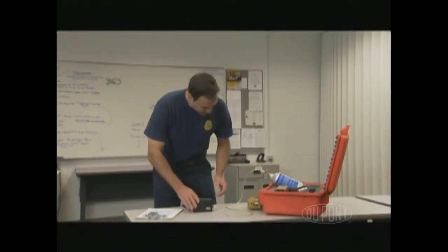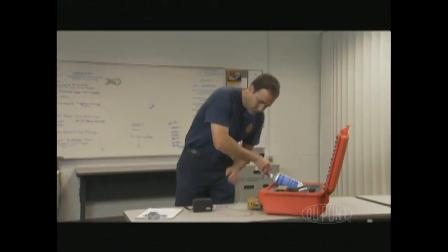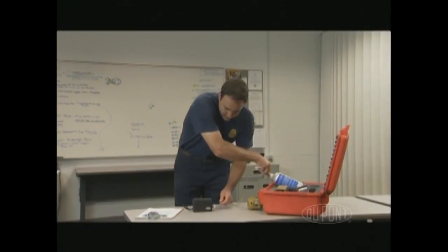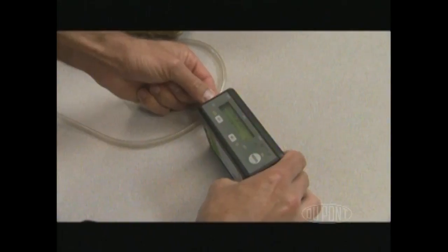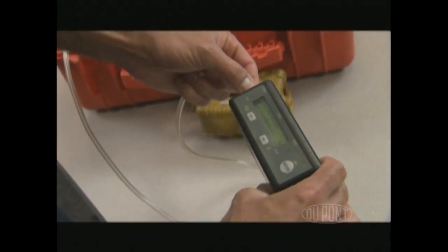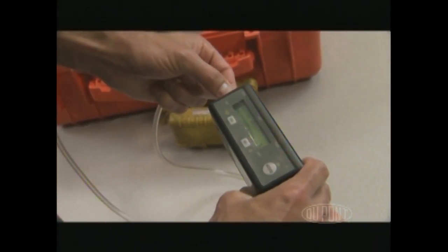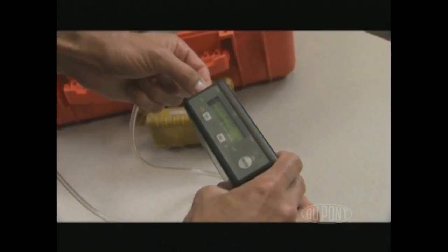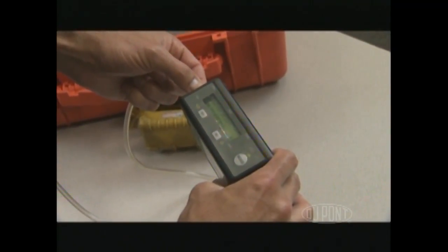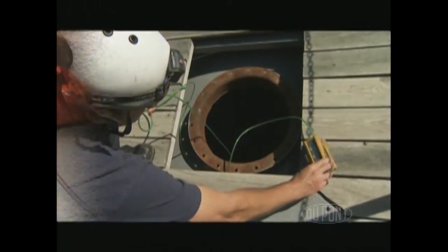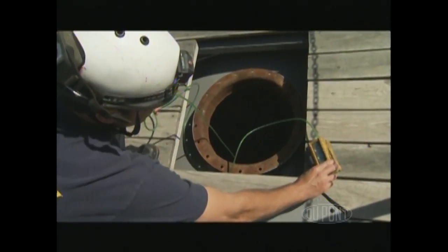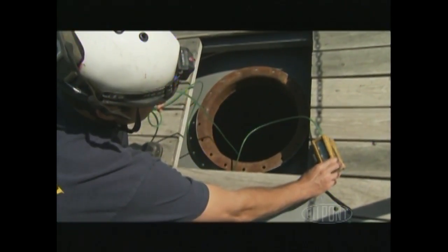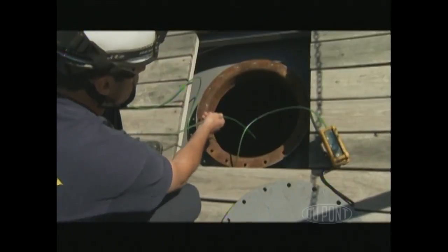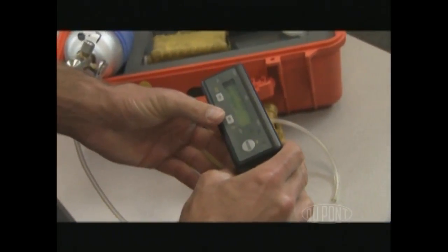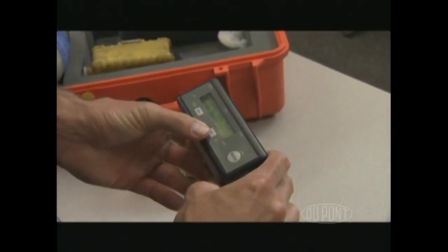Before testing the atmosphere in the confined space, you need to know that your testing equipment is accurate. It needs to be calibrated. Instruments that aren't calibrated properly can become inaccurate over time and lead to serious incidents. So instrument calibration is vital to worker safety. The only way to guarantee that an instrument will detect gas accurately is to test it with a known concentration of gas. This exposure will show whether the sensors are responding accurately and whether the alarms are functioning properly.